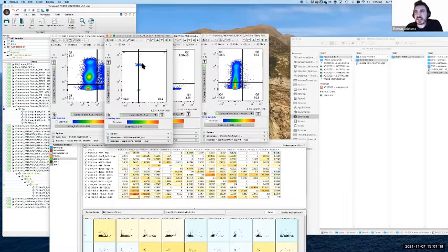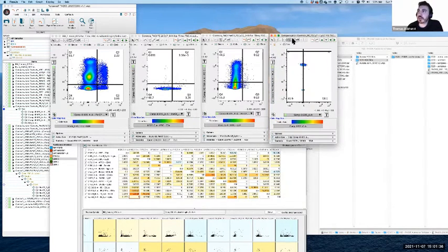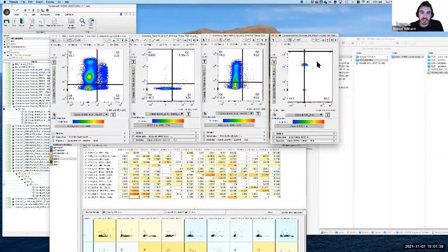And so what I suspect is that, within the tolerance that the calculations have, it thinks the single stain has been corrected sufficiently, but it's just gone a bit too far in the real sample because we haven't given it a bright enough single stain control to map that full range properly. So if I was to hazard a guess, that would be my assumption. I probably need to go back and do a single stain control that has brighter signal. Either I can use a different type of bead, like there are some capture beads which have larger numbers of capture sites so you can get some more signal.